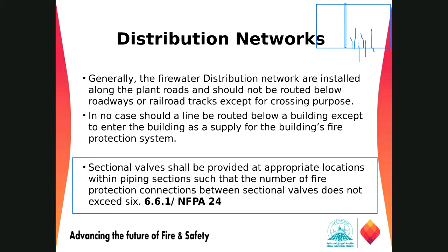So here we have to put one control valve at this location and one control valve at this location, so that in case of fire, we don't have to shut down the complete plant. Just shut down these areas, close these two section control valves, and do the maintenance in these areas, right? And all other areas will be in service. And based on some requirements, while doing the maintenance in an area, we may need temporary fire trucks with water and all to fight the fire if anything happens during those times.